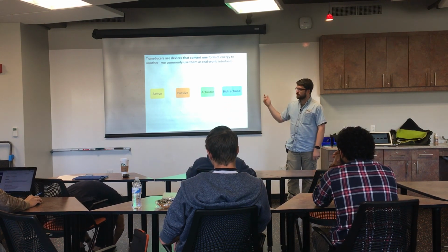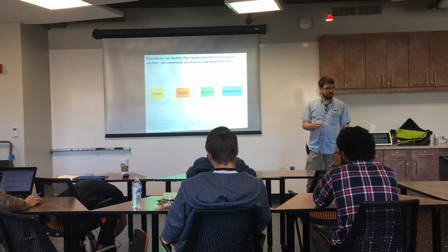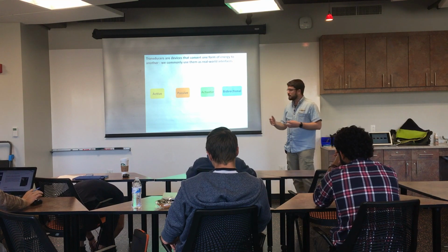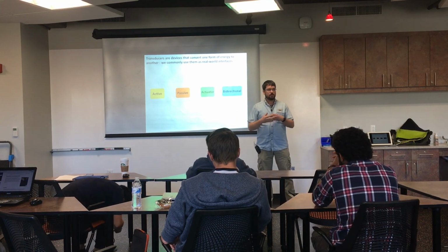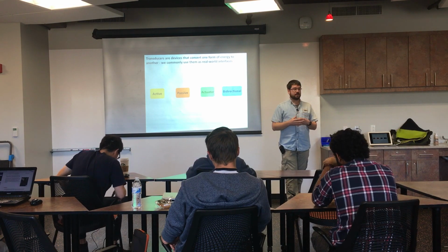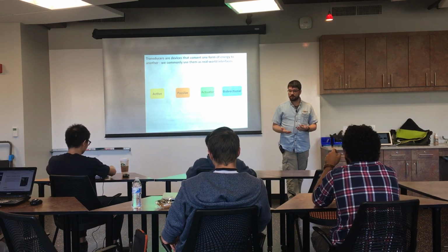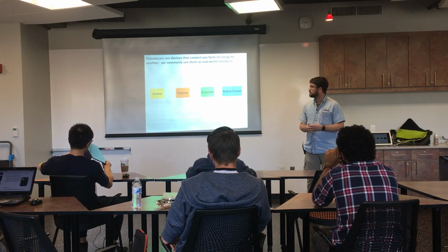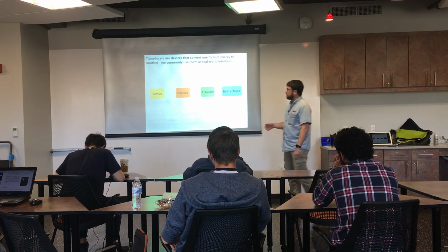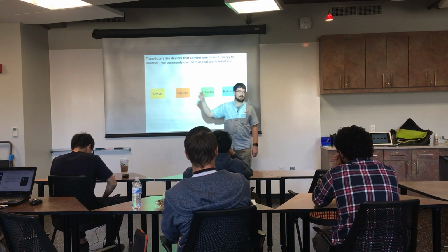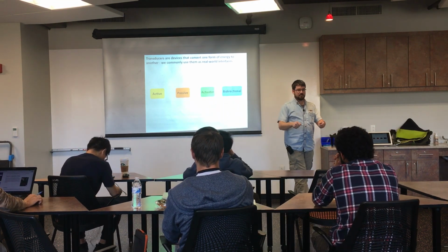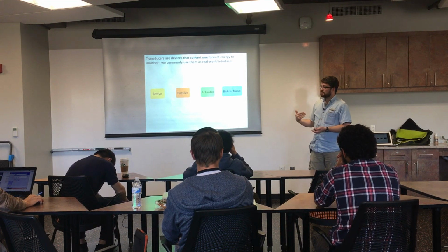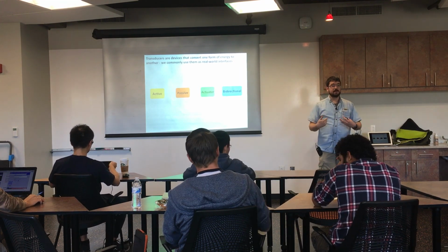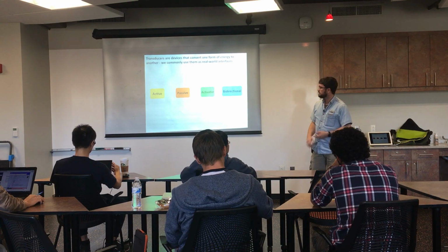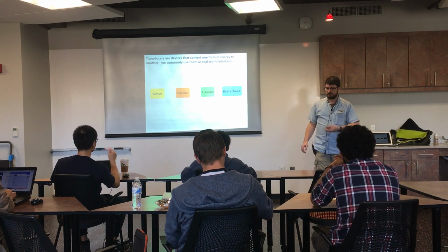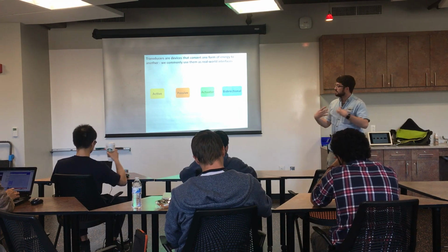And if somebody uses active or passive transducer, you should make them clarify what they mean, because they mean different things to different people. In some cases, an active transducer would be we're sending some kind of a signal into whatever we're trying to measure. It's like active source seismic, sort of. And passive would be we're just listening to the system. From an engineering standpoint, generally when we mean an active transducer, it means we have to put energy into the transducer. So we have to hook it up to some power source and excite it. And a passive transducer is something that just sits there and we can get something directly out of, like a thermocouple, say. And bidirectional transducers are transducers that can either be a sensor or an actuator.